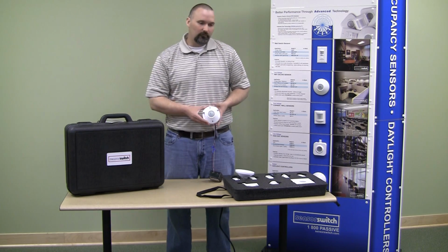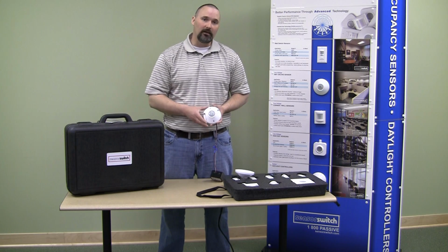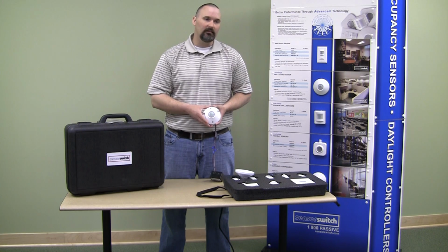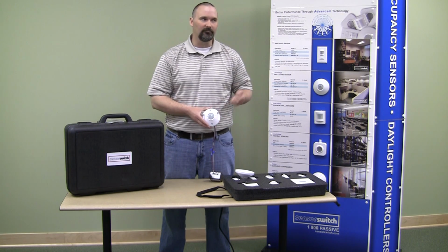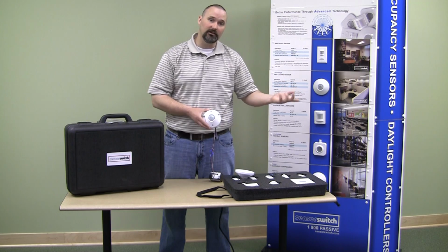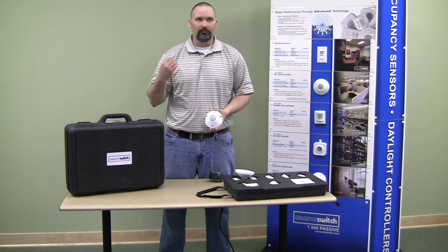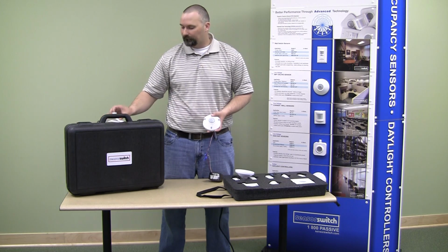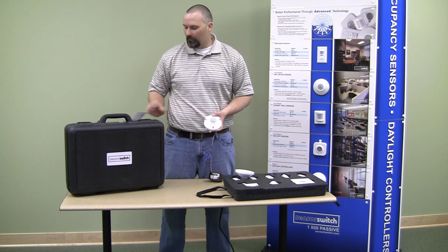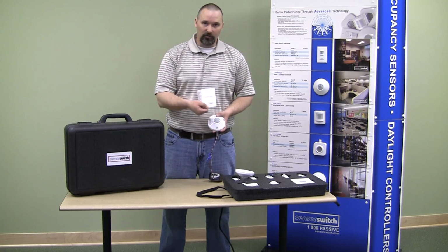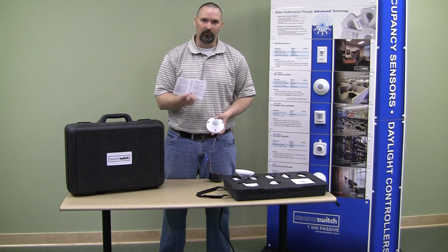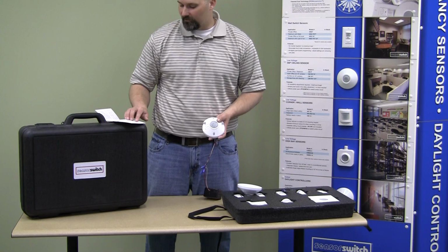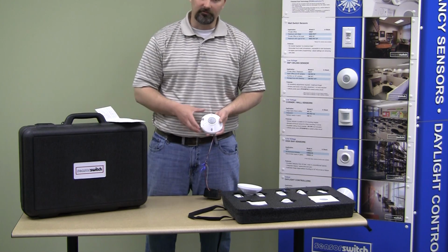The other thing that we can do through the push button programming is detune that microphone. The reason we might need to do that is if we have a space, like a classroom, where they leave the door open and students are walking in the hallway, something along those lines, the microphone will pick up that noise and keep the lights on. So the way that you detune the microphone is we would go into our occupancy sensor programming guide. This is available on the web, and it also comes shipped with the units. We would go into function number 12 to make that microphone adjustment.